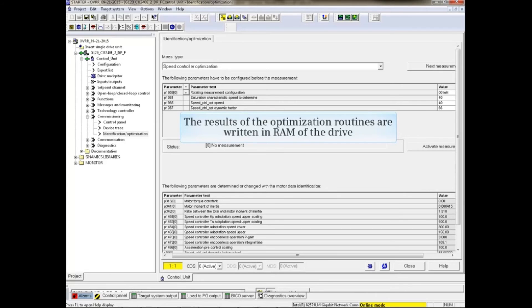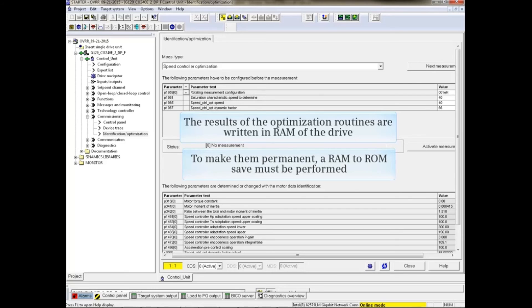The results of the optimization routines are written in RAM of the drive. To make them permanent, a RAM to ROM save must be performed.